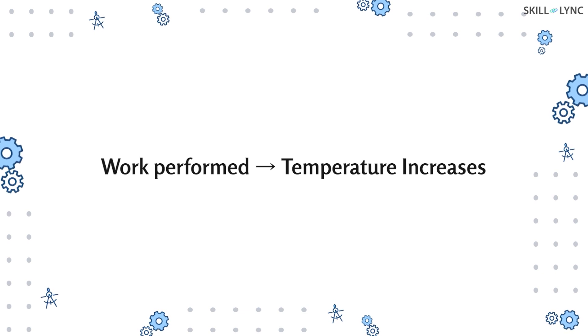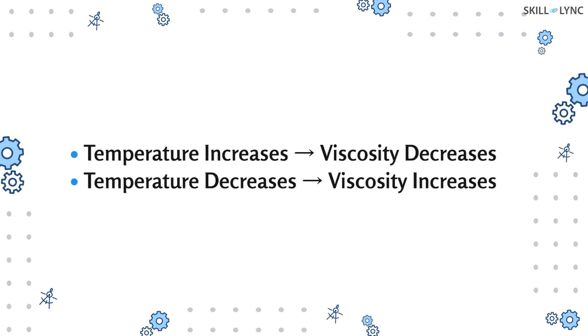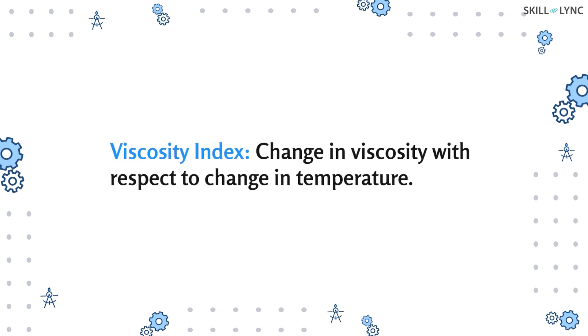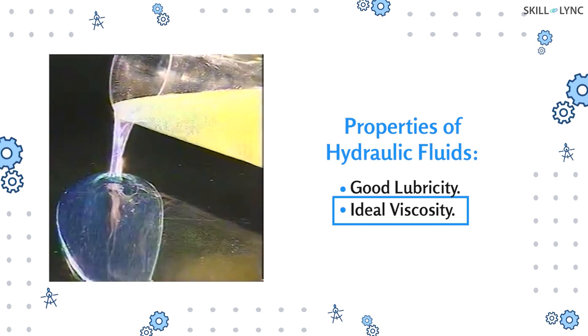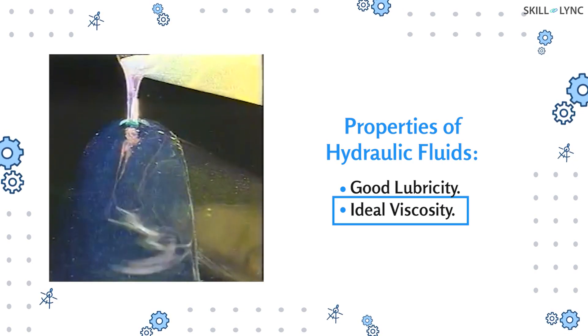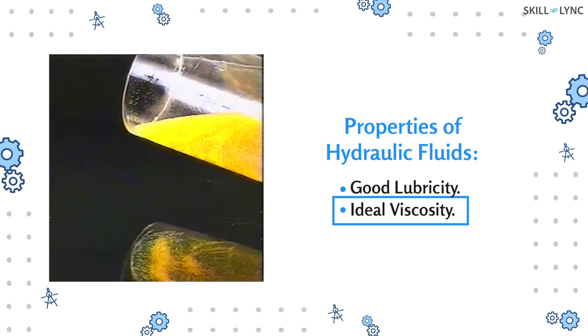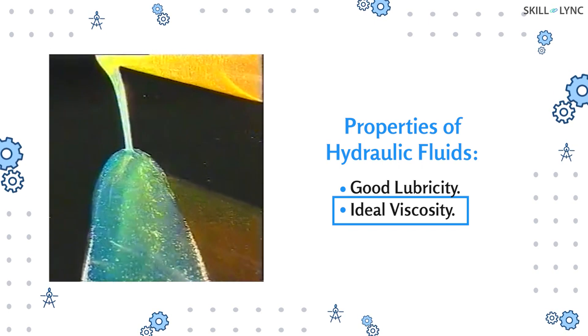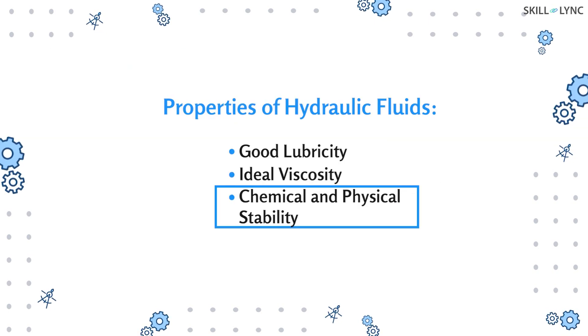As the hydraulic system performs work, the temperature of the system rises, which affects the viscosity of the hydraulic fluid. On increasing the temperature, the viscosity of the liquid decreases, and vice versa. This change in viscosity due to temperature is measured by the viscosity index of the fluid. A hydraulic fluid with a low viscosity index will have a large change in viscosity with the corresponding change in temperature. On the other hand, a fluid with a high viscosity index will have a small change in viscosity.